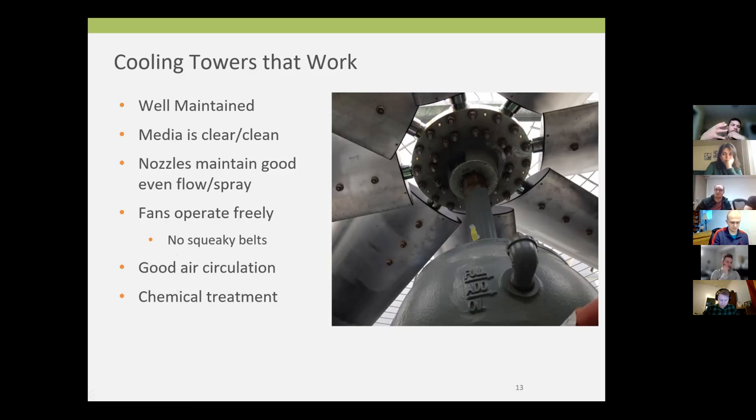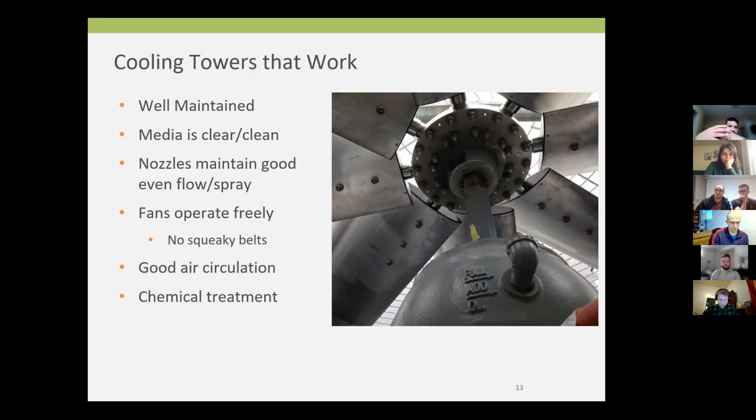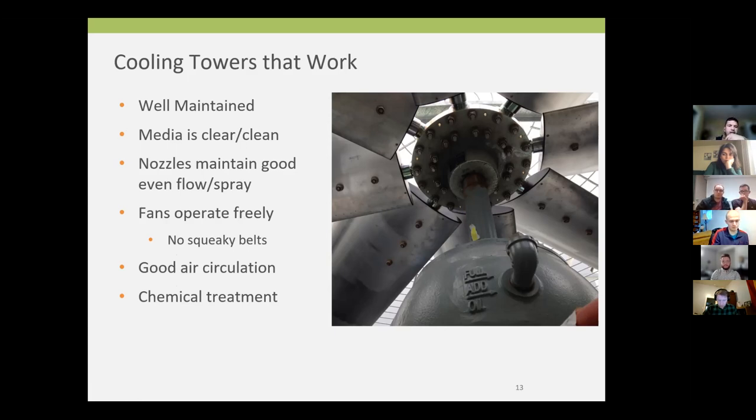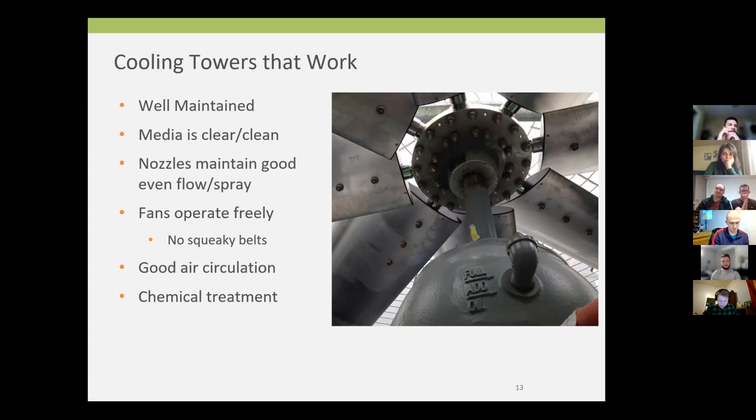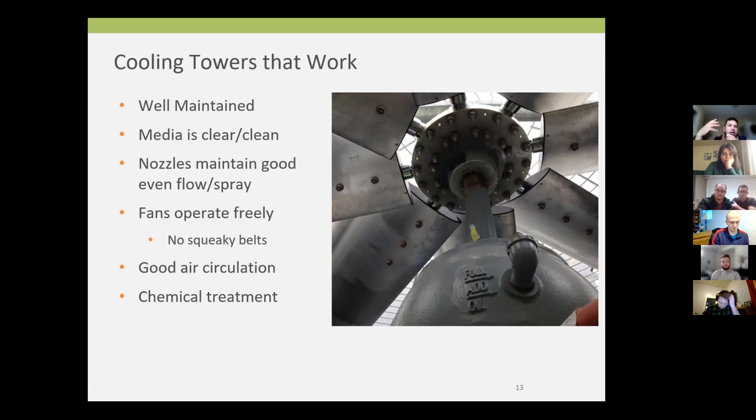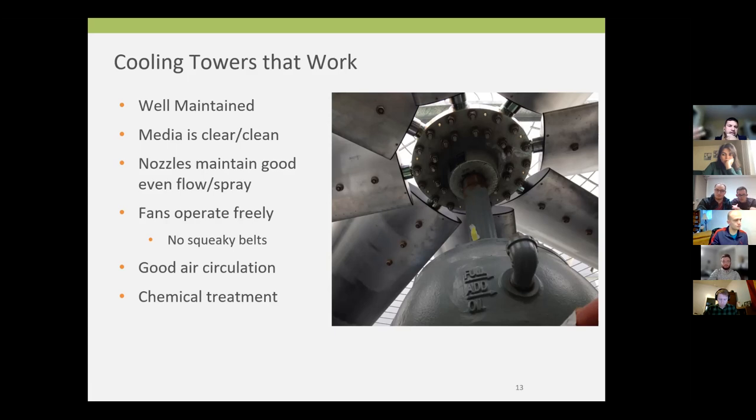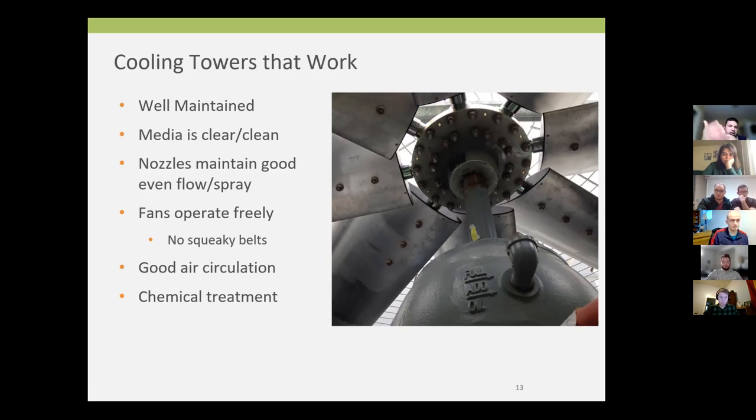You want to make sure that those nozzles are clean. And if you look at the showerhead in your bathroom, you'll see that on the showerhead, you may have a little bit of, if you press on it, you may get a little ring of white material on it. It's just the solids and dissolved solids slowly scaling up on your showerhead. You can just, with your thumb, move them out. That happens to nozzles. Your showerhead is basically a collection of nozzles. So if you see that, just take that 10x, and now you've got that happening there. They use chemical to treat that water. So there is a chemical that is added to it. That's going to be there on site. So that way they keep that pH and all of that in the water treated. Make sure your fans are operating freely. No squeaky belts. No broken blades. Next slide, I'll show you what happens to that.